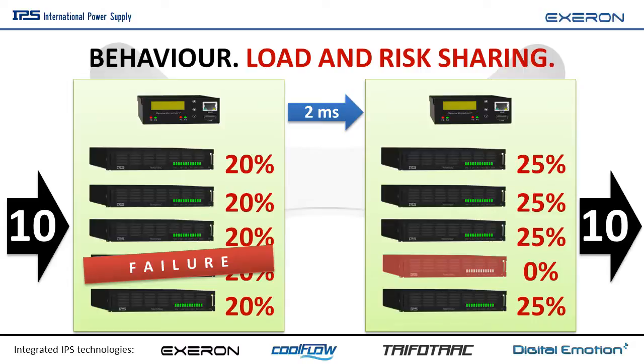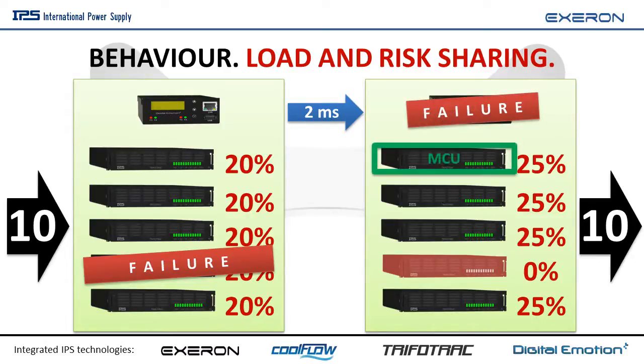What happens in case of MCU failure? Nothing. Because each module is equipped with a microprocessor, in case of MCU failure, because of the network structure of the system, the next free module in the communication channel will take control of the whole system. The main principle implemented in the system concept: whatever happens, a full system stop is impossible.